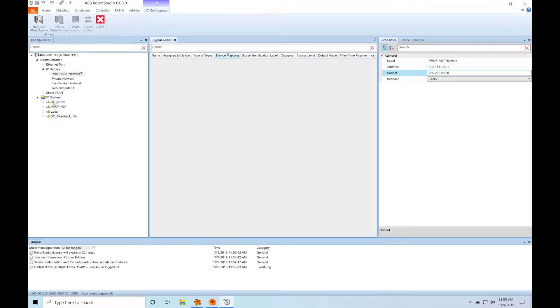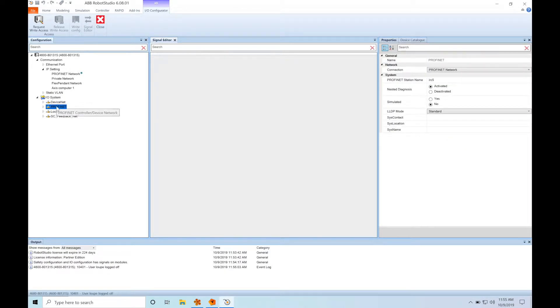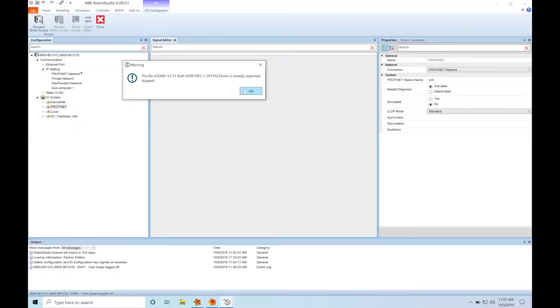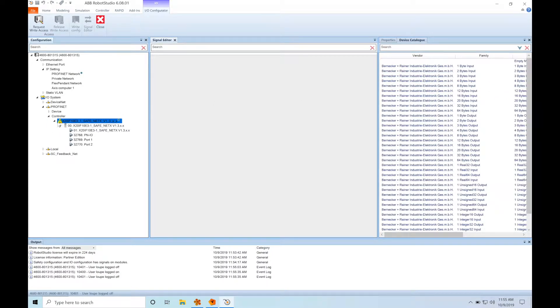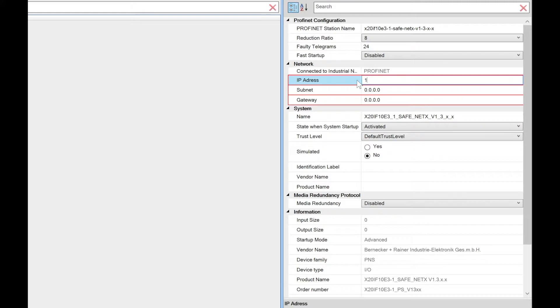Now we're going to set up our ProfiNet controller by importing a GSD file that I got from B&R. It's going to tell me that I already have it installed, so it's going to skip. Now it's going to give us a list of controllers to pick from, and we're going to pick the one that has 'safe' in the name. Once we've added our controller, we have to configure it by giving it an IP address. This IP address has to be on the same subnet as the IP address we configured for the ProfiNet interface, so in this case I'm going to use .3.